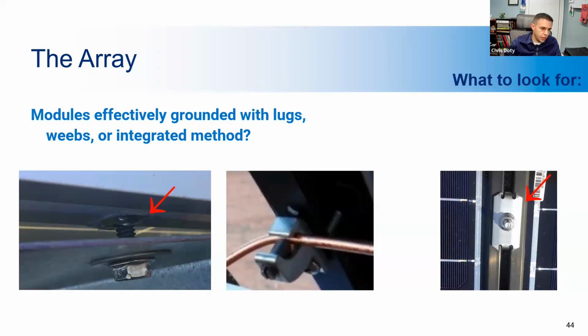And so another thing to keep in mind is, it's critical that you ensure that the equipment that's used to ground and bond the system is suitable for the environment and the application. If the grounding method you use is not rated for the environment, it can fail. And we'll see some examples of that a little bit later. And that would leave the system energized and dangerous.